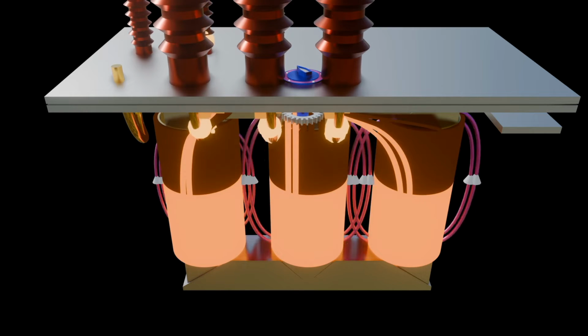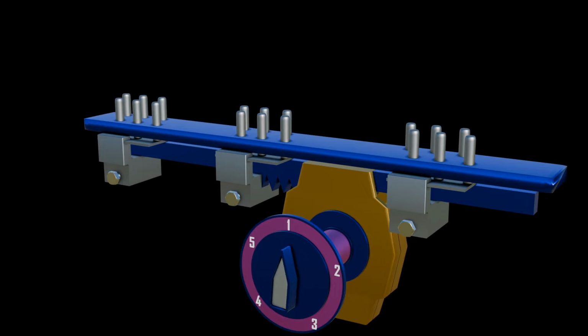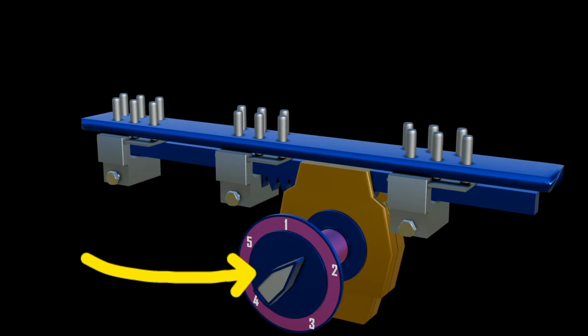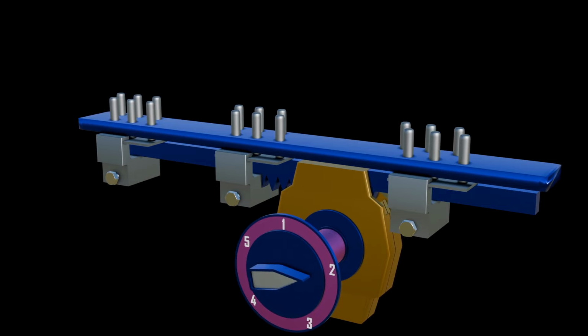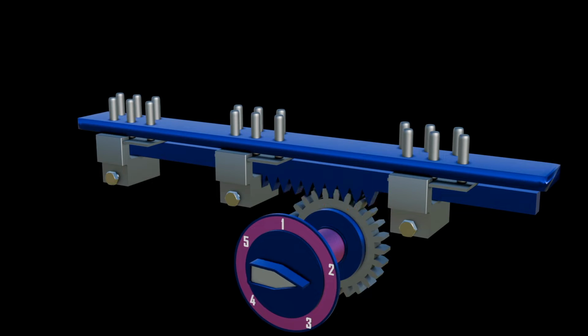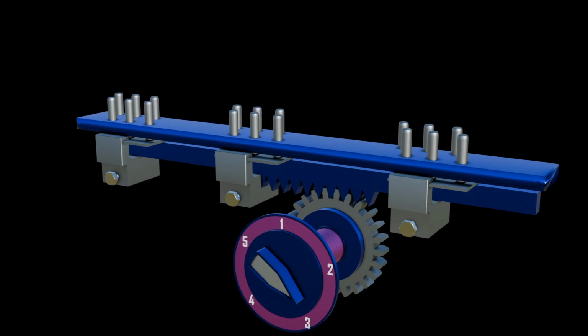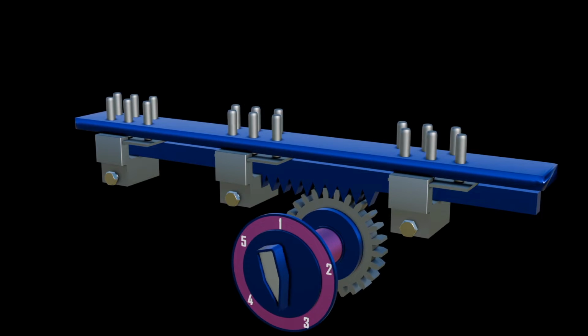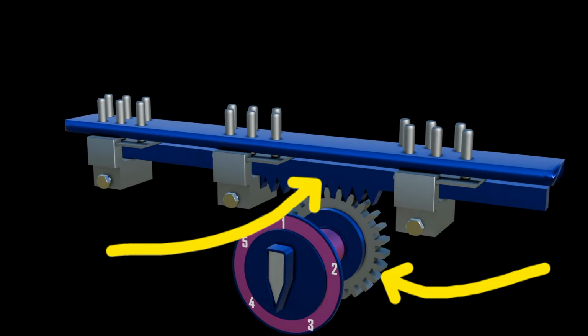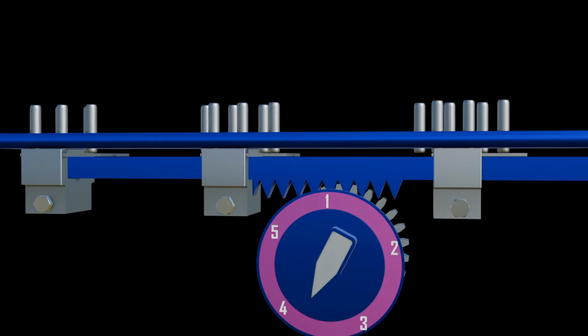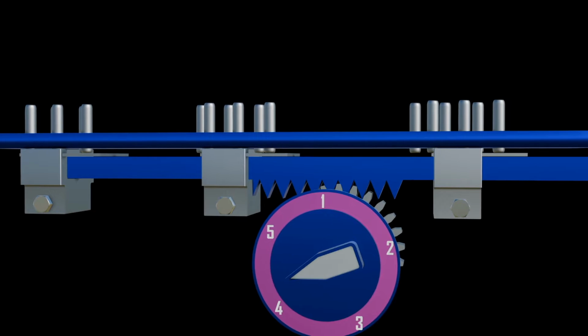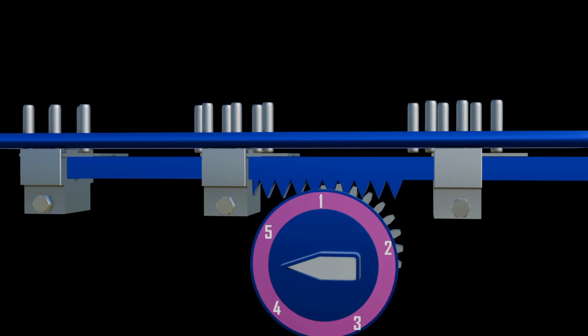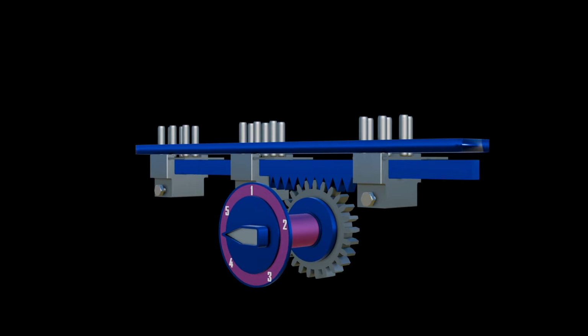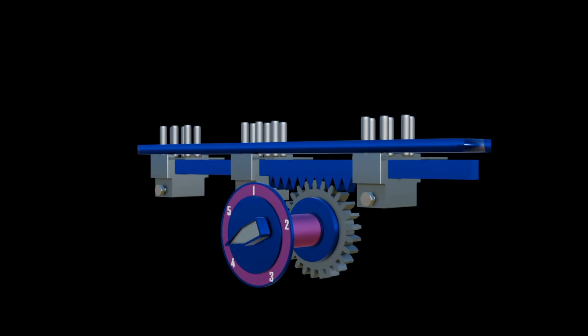It consists of several key components, such as the tap selector switch, which allows for selection of different tap positions, which correspond to different voltage ratios. It is manually operated. The tap selector mechanism physically moves the tap selector switch to the desired position. It consists of a round gear and a linear gear attached to the switch. They work together to translate the rotational motion of the operator into linear motion, which then moves the tap selector switch to the desired position.